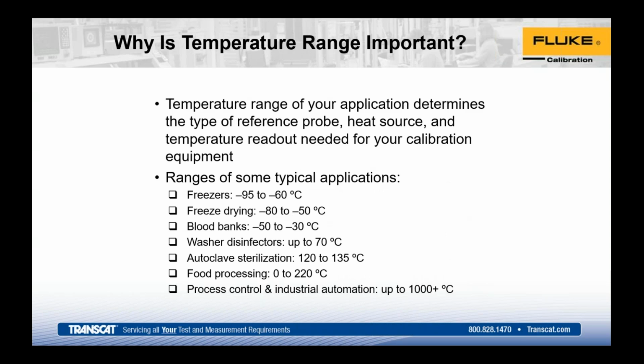As we've gone through, we've seen a few different pieces between baths, dry wells, different probes, and you might ask why range is important. Again, it's just the sensor types - there's such a wide variety, ranging from your base metal TCs to precision TCs or special limits of error, plus loads of different RTD types. You've got typically your DIN class A, B, 1/10 DIN, 1/3 DIN, and then ones that are very specific, like we sell, calibrated to ITS-90. Given how they're built up, they'll have different sheath lengths and stems, and that all plays into the capability of how they can be used.